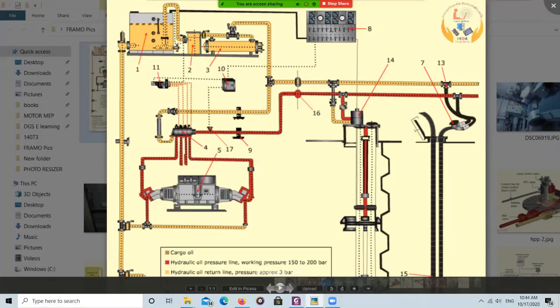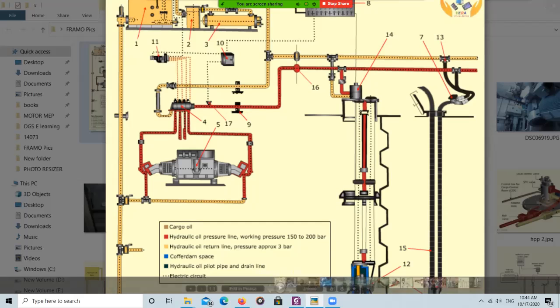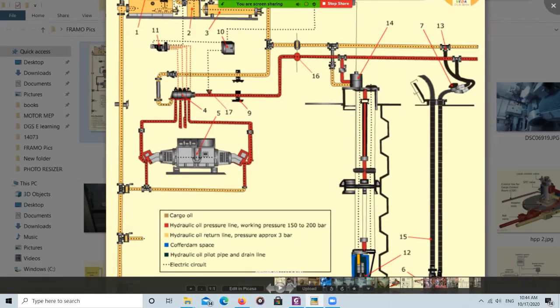The oil flow is: from the hydraulic tank, the oil goes to the hydraulic oil filter. From the filter the oil goes to the oil cooler, which ensures the temperature stays within the desired range. The temperature of the hydraulic oil should not exceed 65°C — 65°C is the tripping temperature and 60°C is the alarm temperature, so the hydraulic oil temperature must be maintained below 60°C.